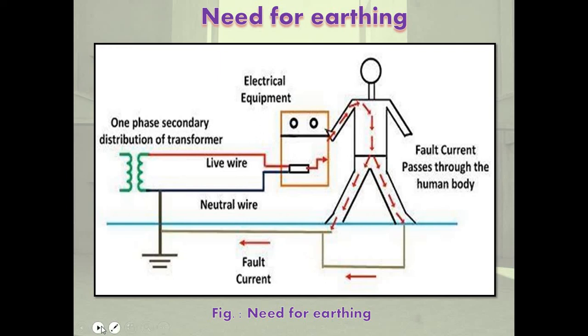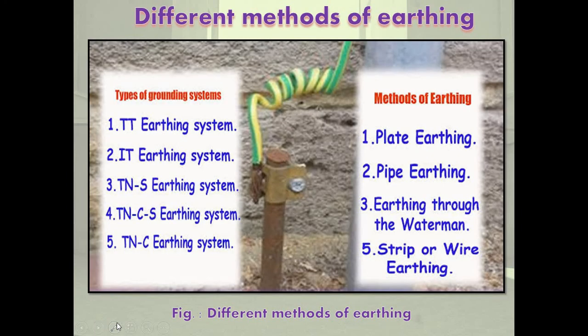Now, these are the different methods of earthing. Types of grounding systems: first is TT earthing system, IT earthing system, TN-S earthing system, TN-C-S earthing system and TN-C earthing system. And methods of earthing: first is plate earthing, pipe earthing, through the water main, and strip or wire earthing. Earthing is the most important in electrical appliances.